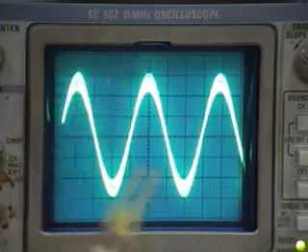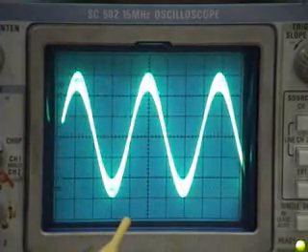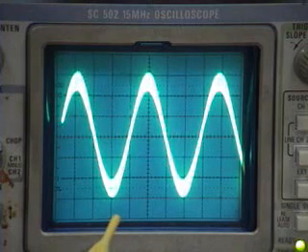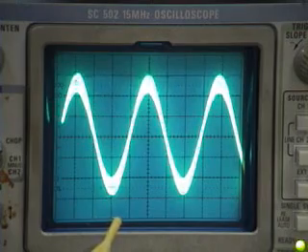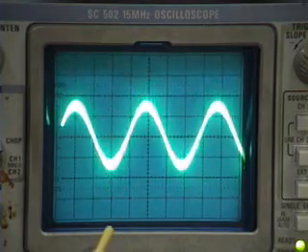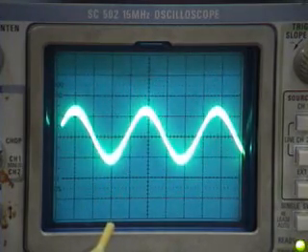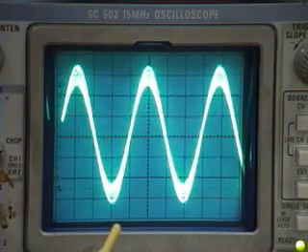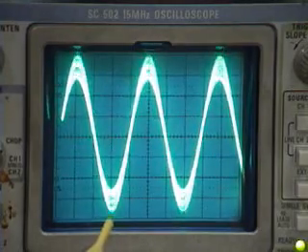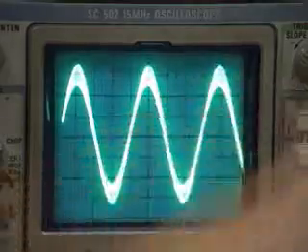What we're seeing here is each magnetic pickup tooth as it passes by. Now, as I said before, the mag pickup amplitude is dependent upon the distance between the mag pickup and the gear. As I back the mag pickup out, you'll see the amplitude decrease. As I increase, it gets bigger and bigger. As I adjust the time rate on the oscilloscope, you'll see that we have some amplitude modulation in here. That's caused by the run out in the gear.